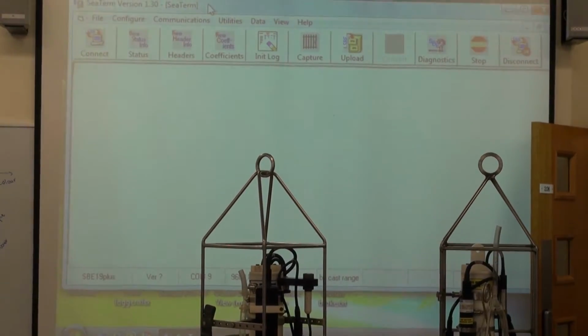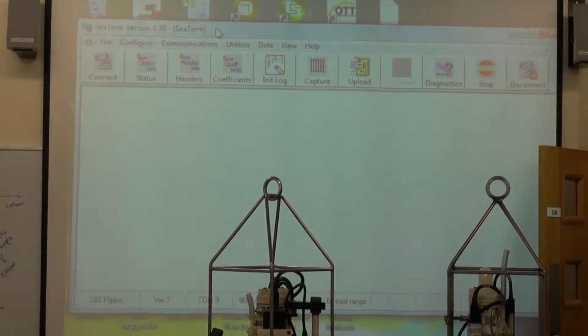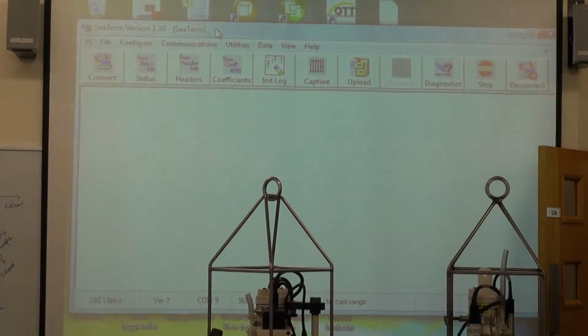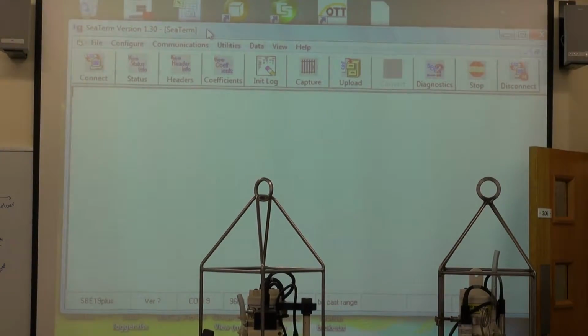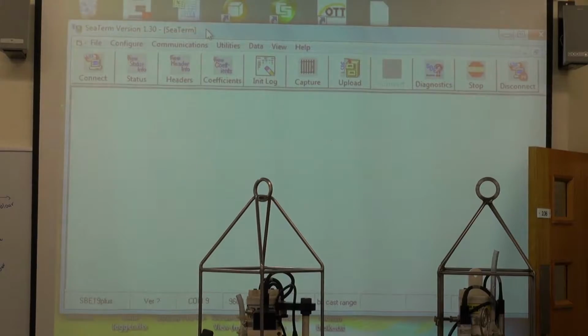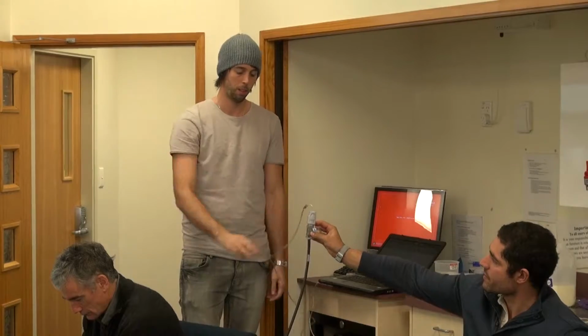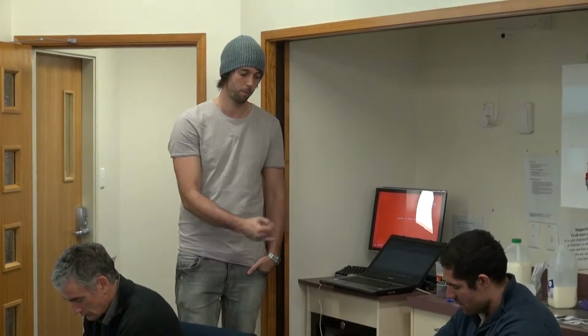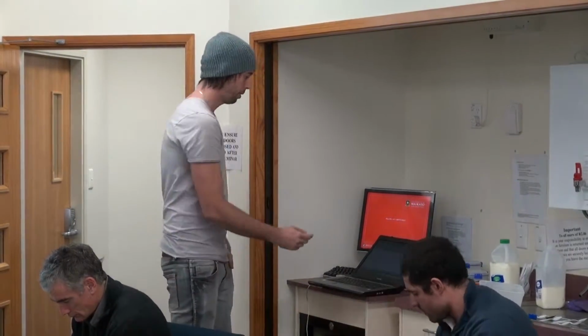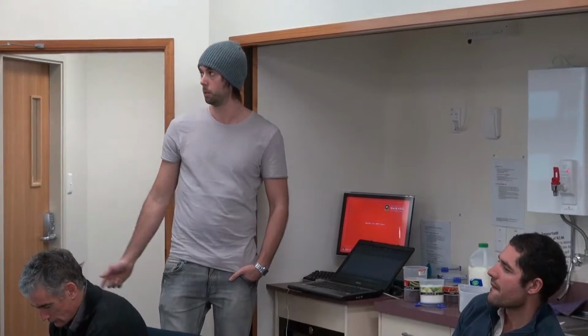Screen resolution's a bit screwed up. What you often run into, similarly with probably the hobo loggers and with any kind of instrumentation, is that in the old days you had 9-pin serial ports on computers. We don't really have these anymore. We have USB ports. So generally to communicate with the instrumentation you need an adapter, like that, USB to serial adapter. And each computer will store what's called a COM port address for each specific adapter. If the software that you're using to communicate with the instrument isn't looking for the right COM port, then it won't be able to talk to the instrument.